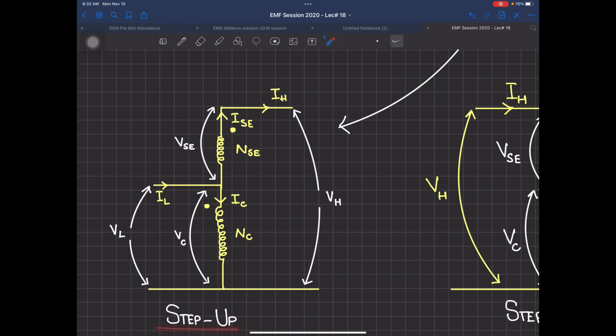How does it step up? You will apply a voltage, supposedly 13.2 kV. This 13.2 kV is applied overall on this side, and on NSE, because you only require a voltage increase of 0.6 kV, 600 volts. So 600 volts will correspond to maybe 40 turns. This one may be equal to 1000 turns.